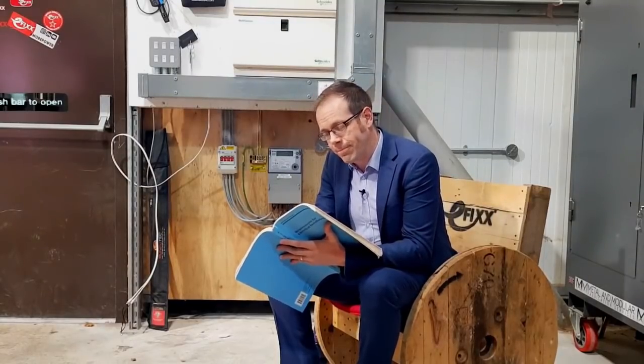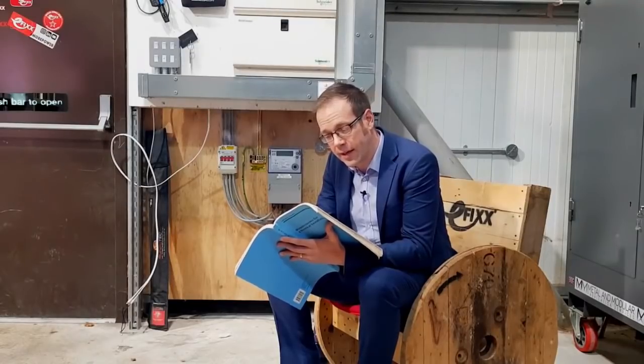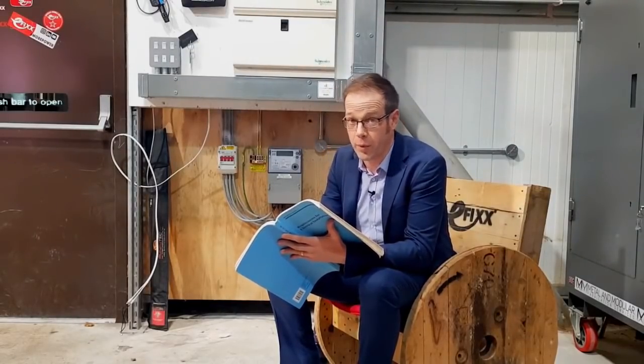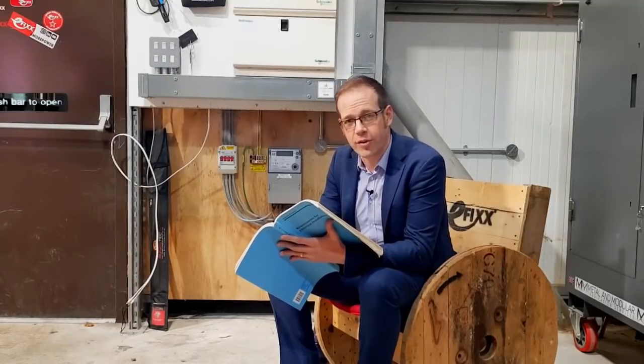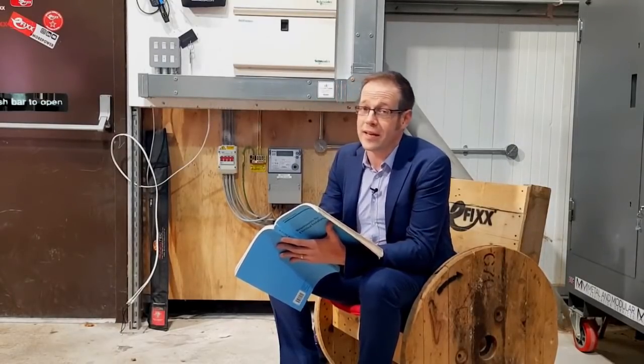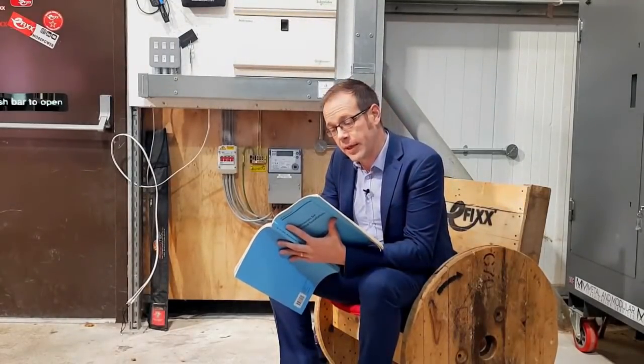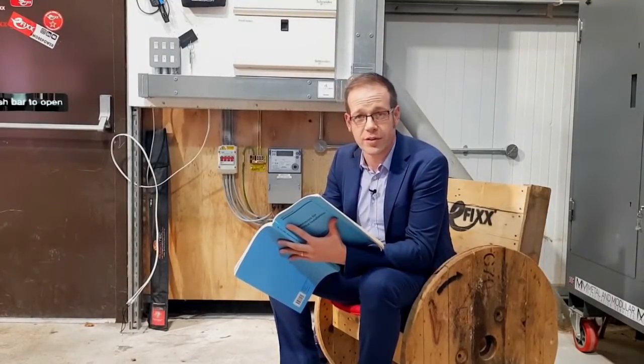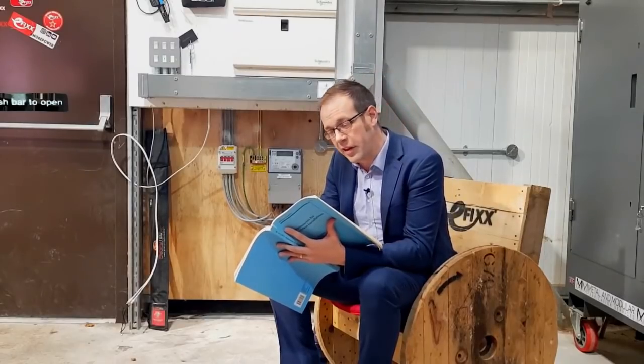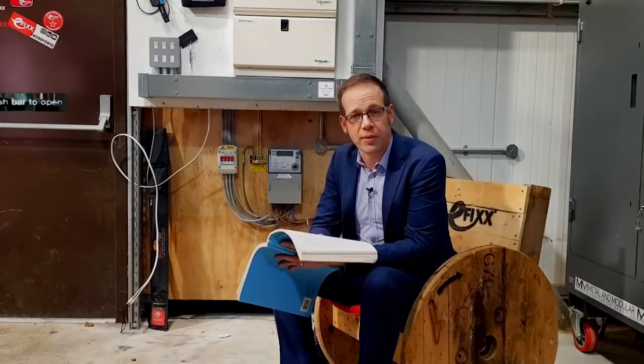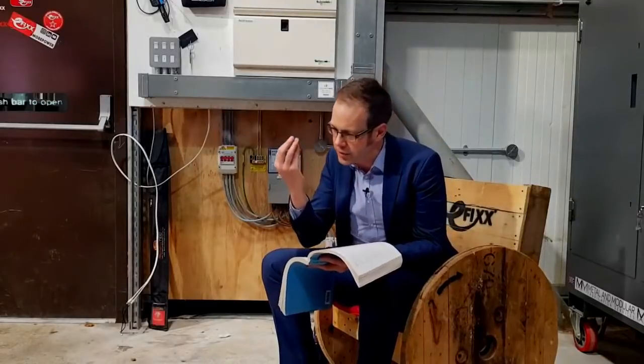In every installation, a main earthing terminal shall be provided to connect the following to the earthing conductor: number one, the circuit protective conductors; number two, the protective bonding conductors; number three, functional earthing conductors if required; and number four, lightning protection system bonding conductor if any - see Regulation 411.3.1.2. Short, sweet, but absolutely loaded with critical information. It's as if the authors of BS 7671 looked at the tree of earthing and bonding and distilled the sweet fruit it bears into the finest and most fiery of spirits.